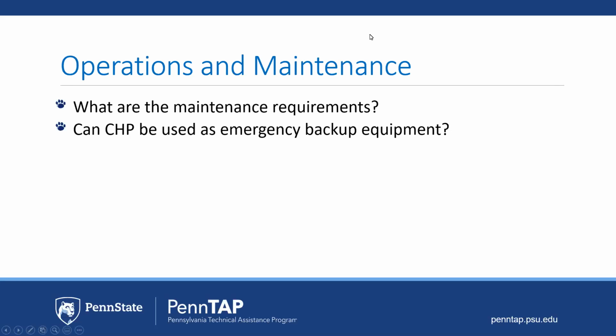For healthcare facilities, there's a requirement to have emergency backup power, typically done by diesel generator, regardless of whether we use CHP or not. For critical care, life safety care, and some major equipment, if there's a disruption in power, the emergency system needs to come back up within less than 6 seconds. So we have to have diesel generator emergency backup for those.